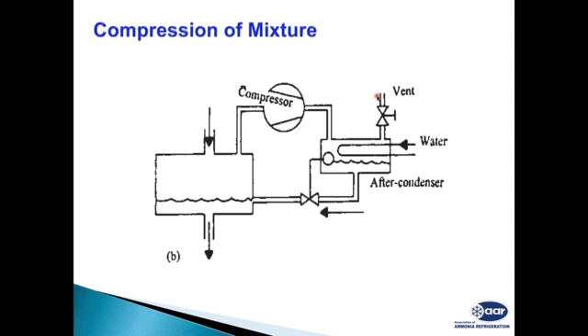Second part, as we talk about automation of the automatic purging system, its advantage over the manual one is that you can do it automatically, online. These purging systems have two types. One uses ammonia, with an external compressor and condensing unit, in which vapors are taken from the ammonia receiver, compressed and condensed in the condensing unit. The condensed liquid goes back into the receiver, and the non-condensable gases are vented. This unit has a separate condensing unit.